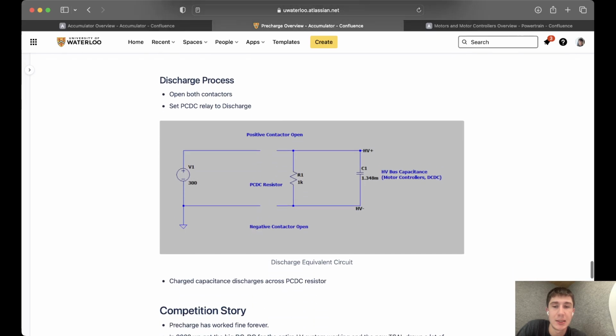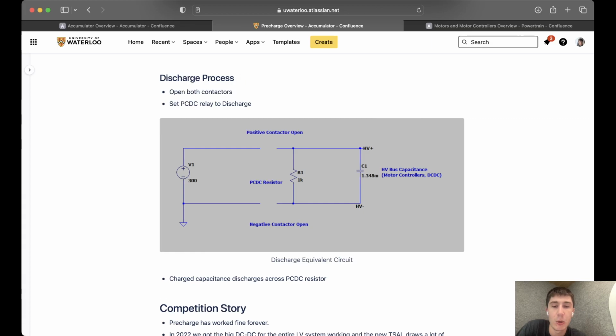Our discharge process is a lot simpler. Essentially, all we do is open both contactors and set our PC-DC relay to discharge. So in this situation, when our capacitor is fully charged, it will discharge across this resistor until 0 volts is on our high voltage bus.